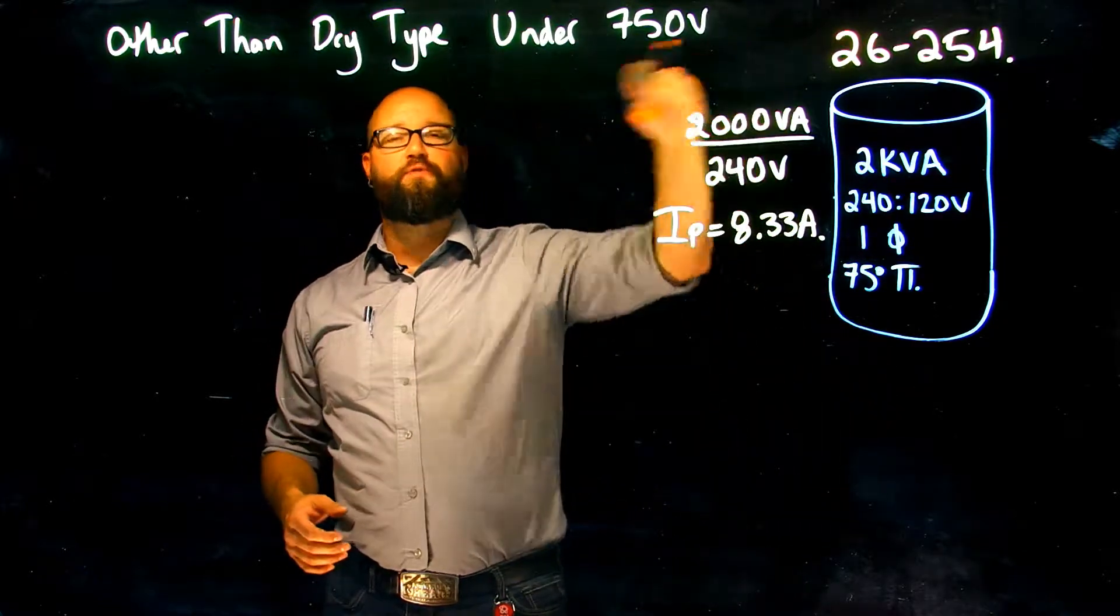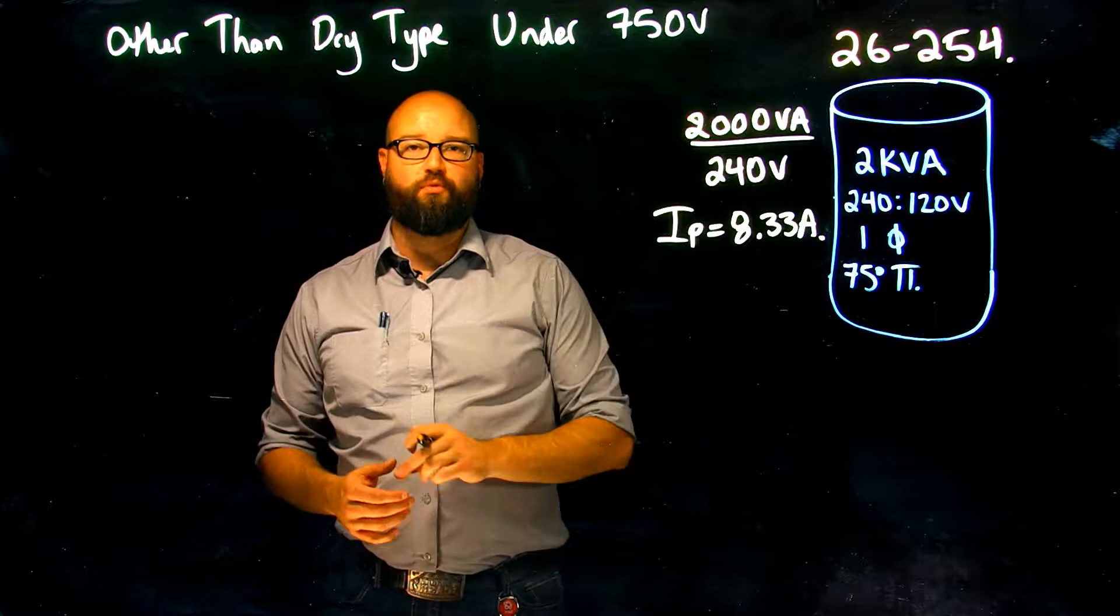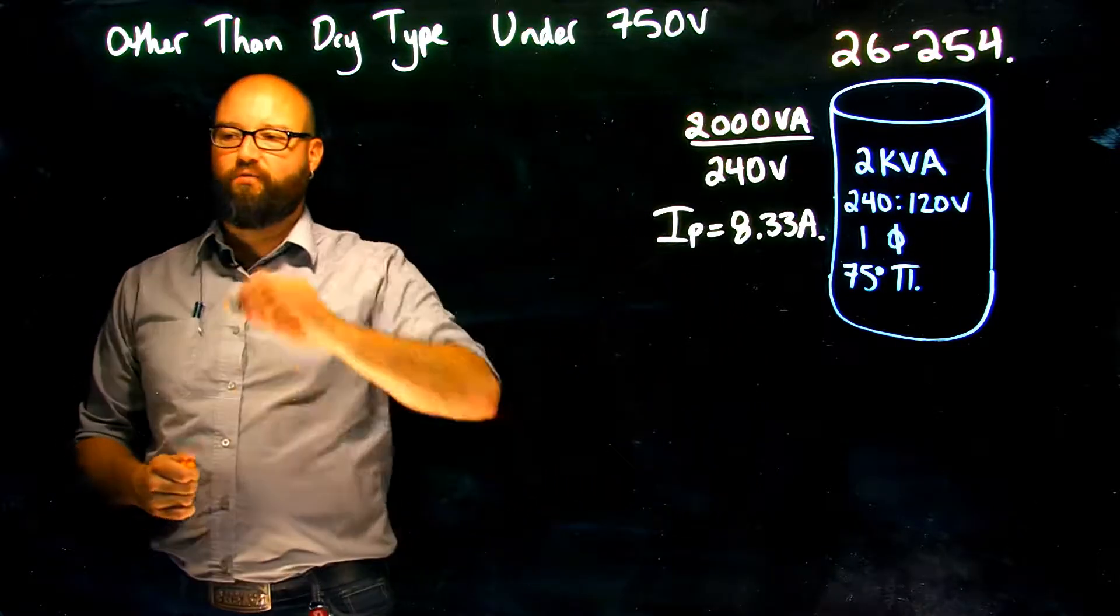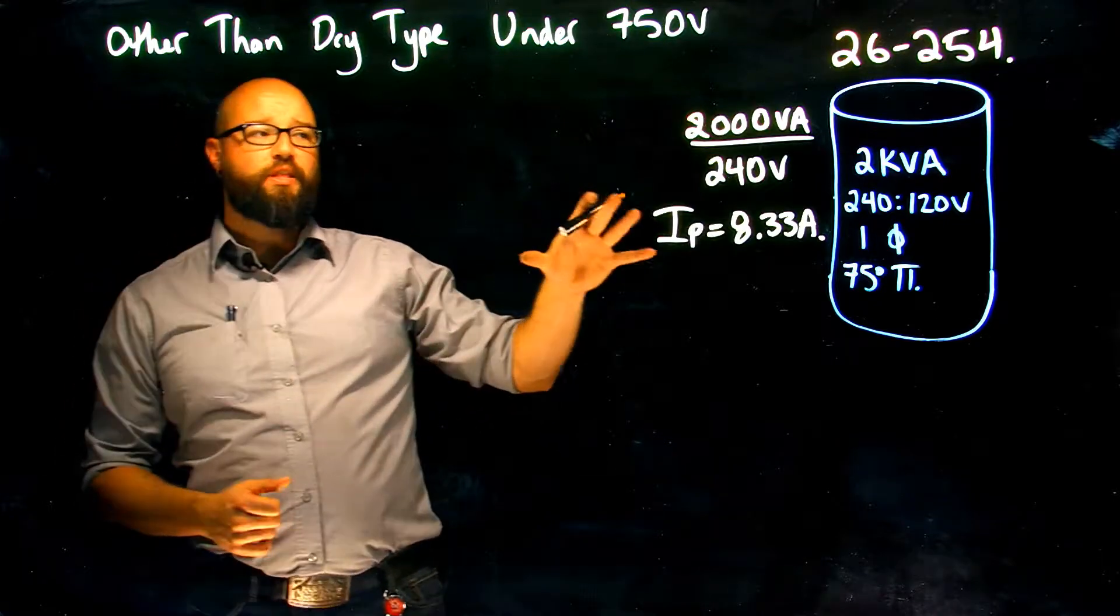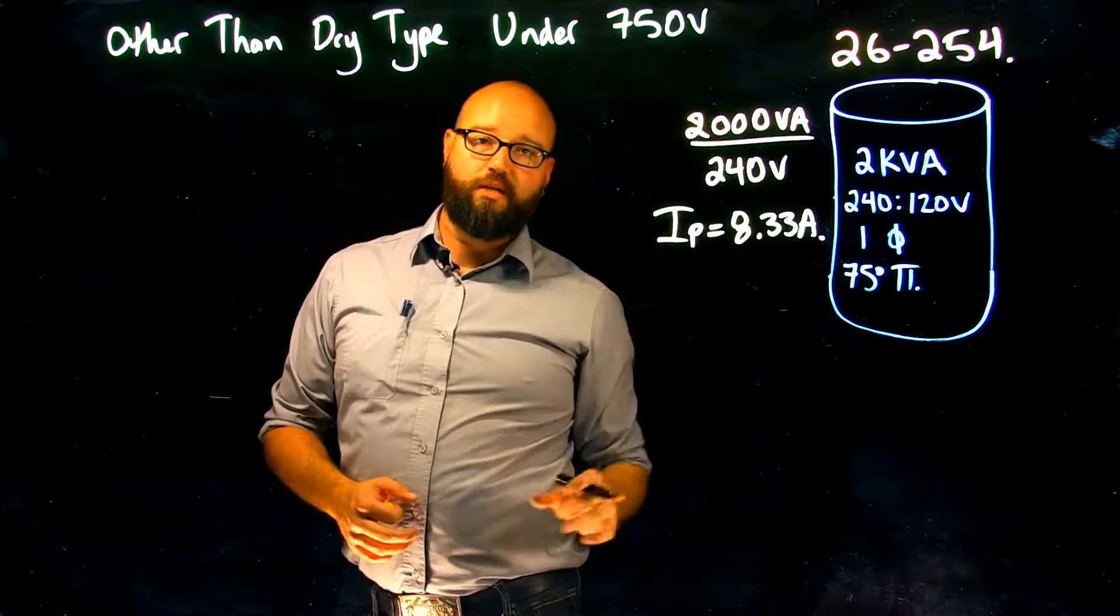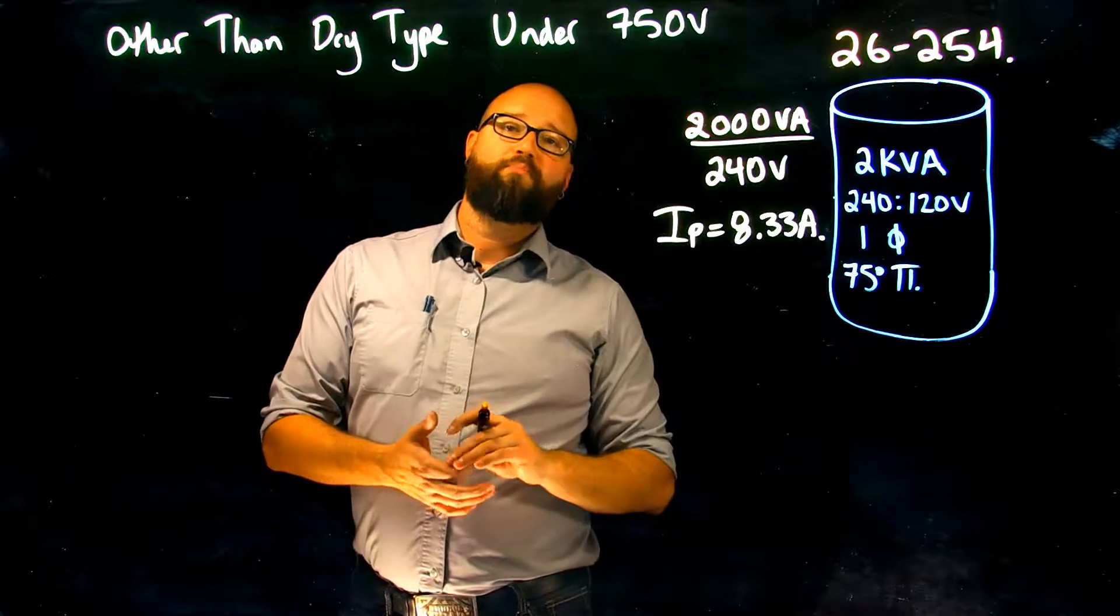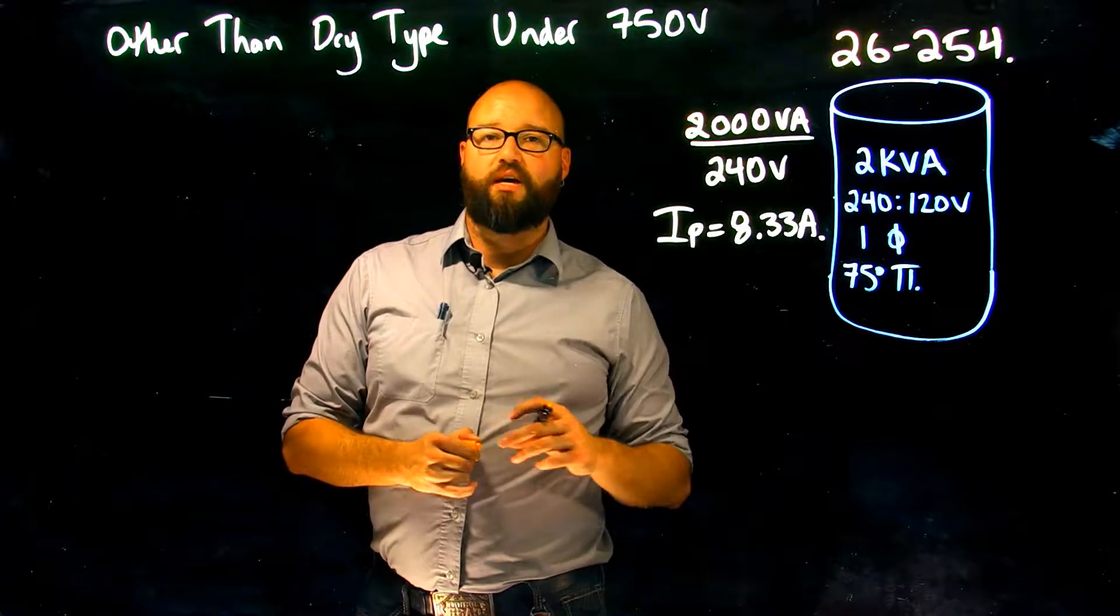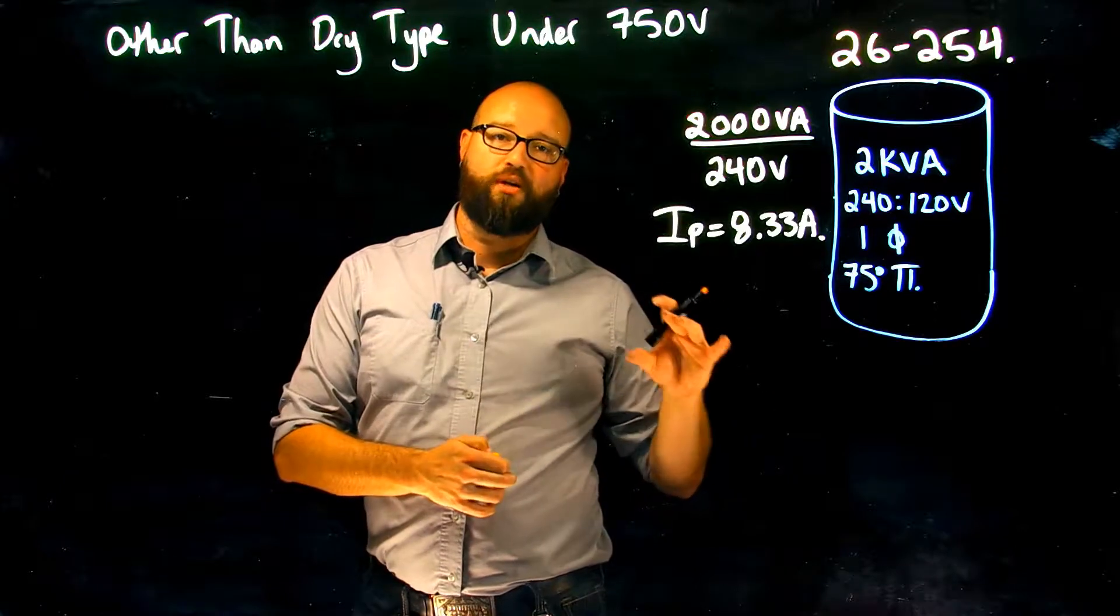We need to do a little bit of reading in 26-254, which is our reference for this calculation. There's a couple of things. If we look at 26-254, it tells me that if I have a rated primary current, sub rule one says for a rated primary current, we're going to take 150 percent of that rated primary current and choose an overcurrent rated or set at not more than that value.